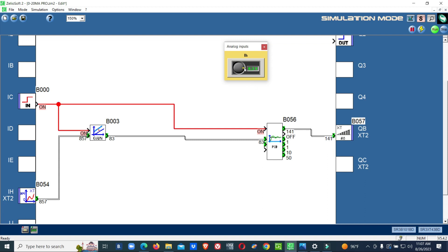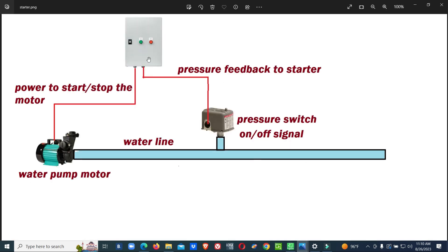Once the pressure drops below the set point again, the output will increase and try to maintain the desired set point pressure in the pipeline. This PID control is not only used for pressure in pump applications — it can also be used for maintaining temperature. Instead of a VFD, a thyristor can be used with an analog input to control the heating level of heaters — for both heating and cooling control. The main advantage of the PID controller is that it reduces electricity consumption, mechanical damage, and extends the life of the equipment.